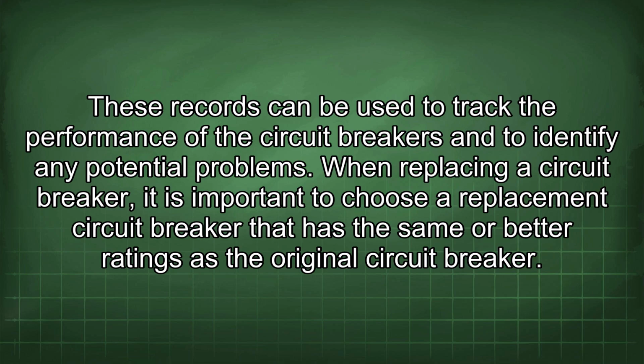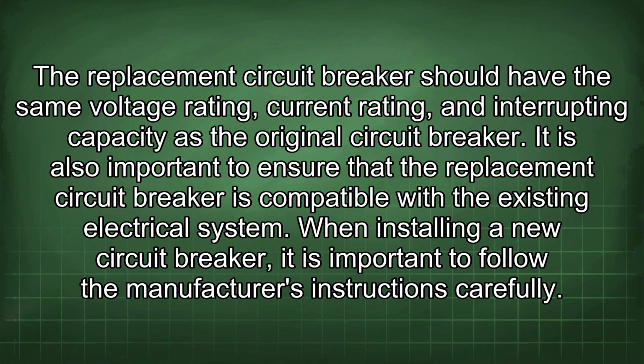When replacing a circuit breaker, it is important to choose a replacement circuit breaker that has the same or better ratings as the original circuit breaker. The replacement circuit breaker should have the same voltage rating, current rating, and interrupting capacity as the original circuit breaker. It is also important to ensure that the replacement circuit breaker is compatible with the existing electrical system.